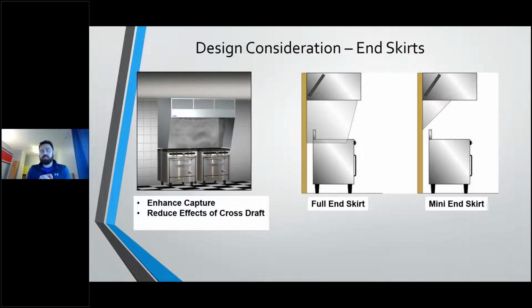So in my experience, cooks don't necessarily like end skirts, because if you think of a cook in this image, and he's got a big pot sitting on the back of this range, and it's boiling, he's making soup or something. When he goes to grab that pot, he or she can't just swing to their left and put that pot down on a table sitting to the left, because there's an end skirt blocking it. So they've got to take the pot off, take a couple steps back, move over, and then put it on that table. So they can impede operations. And if that's a concern, that's when you would use a mini end skirt, which will typically increase capture by about 10 to 20%, depending on the appliance lineup.